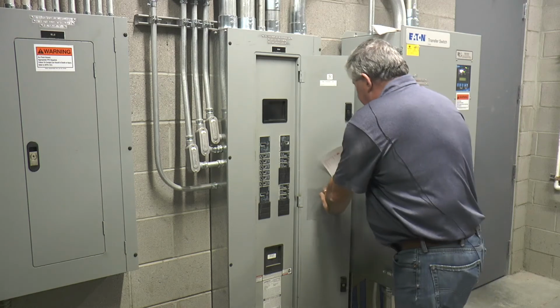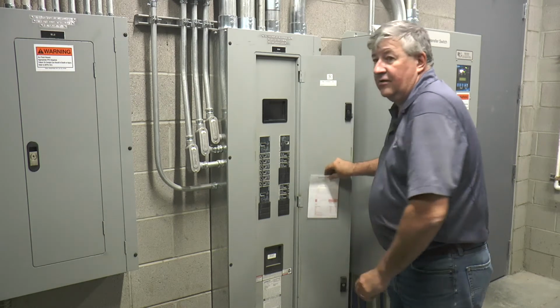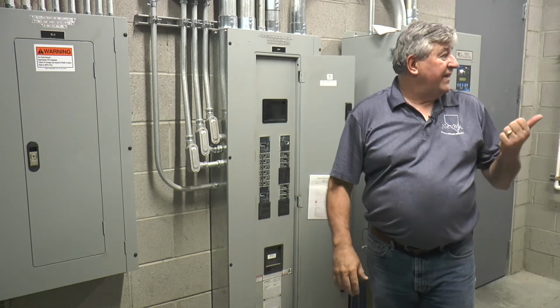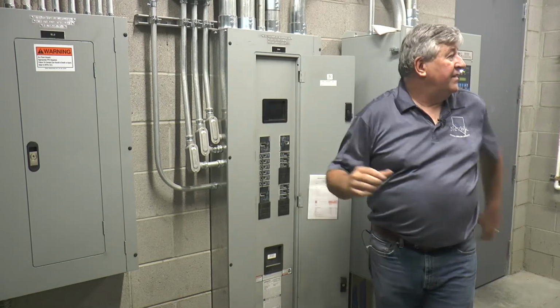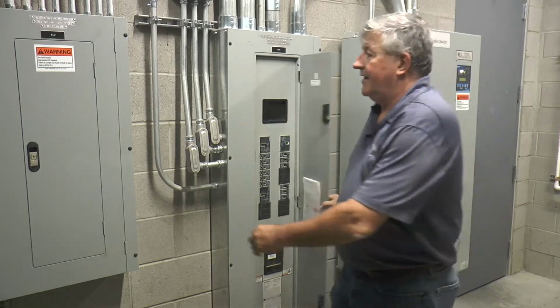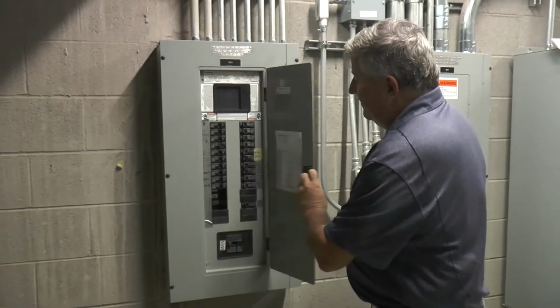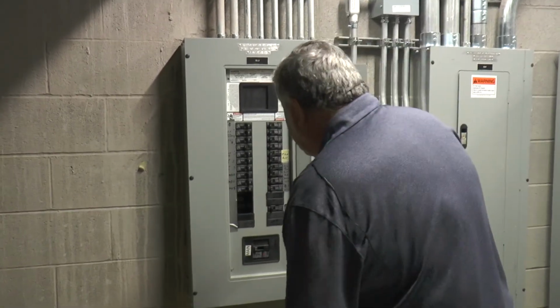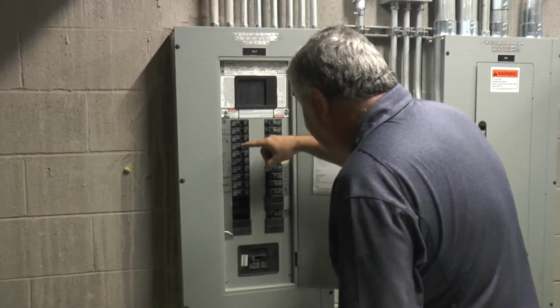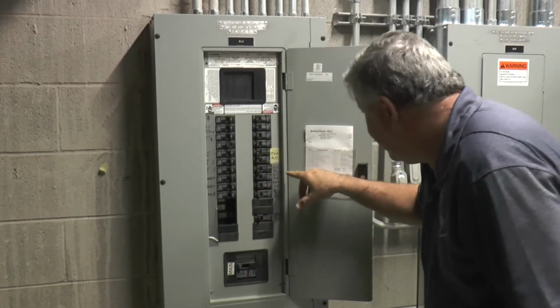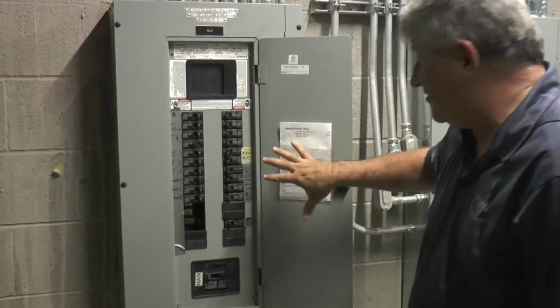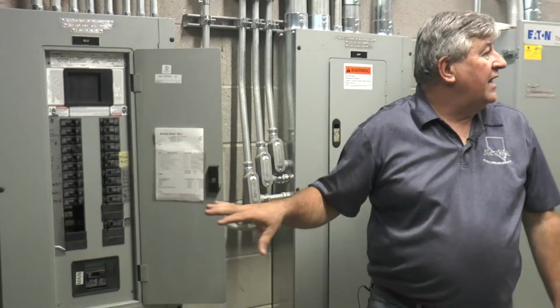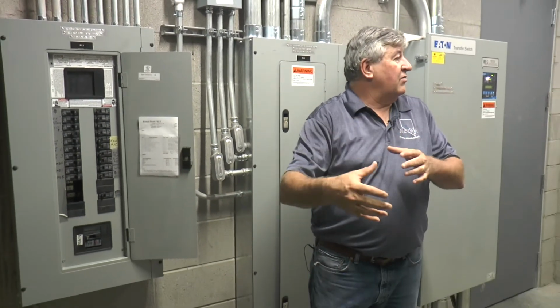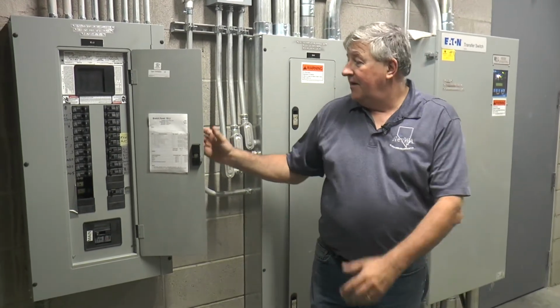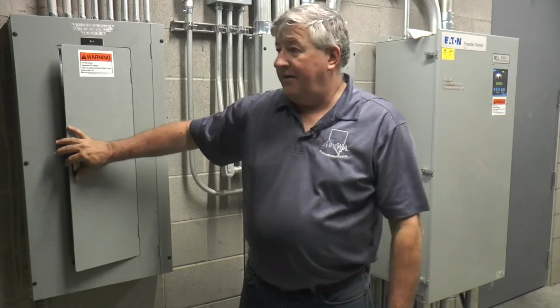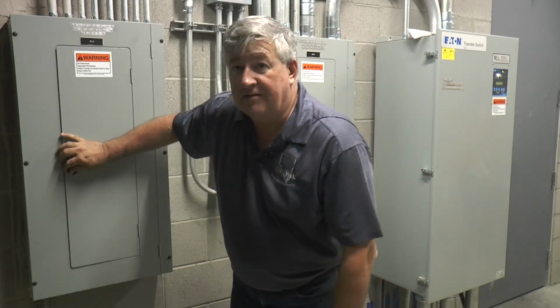So that's what this is legally required to pick up all those loads. So all the stairwell pressurization fans that you have are being fed from this transfer switch. Then all your low voltage stuff: fire alarm, fire command, pumps, MDF room, fire pump room, AC. These are all the low voltage loads keeping those rooms and that equipment up and running. And that's all I have for that. We'll go do the fill station and we're done.